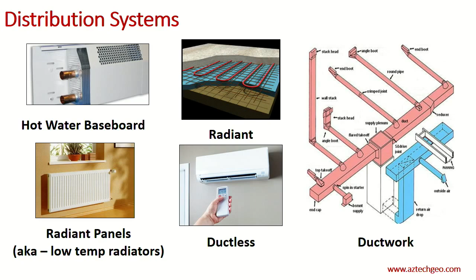So any system that has low temperature hydronics will operate more efficiently than one that has that nice big surface area. Ductless systems can be both for geothermal and air source. There's versions of those. Often if it was a ductless mini split, that's a refrigerant head there. That's either hot or cold, depending on the season. If it was a geothermal, it's usually a water-to-water where we're sending either hot or cold water to that system. Geothermal systems tend to be central air systems is the most common. I'd say maybe 20% or less of our systems are a water-based system where the distribution system is water.